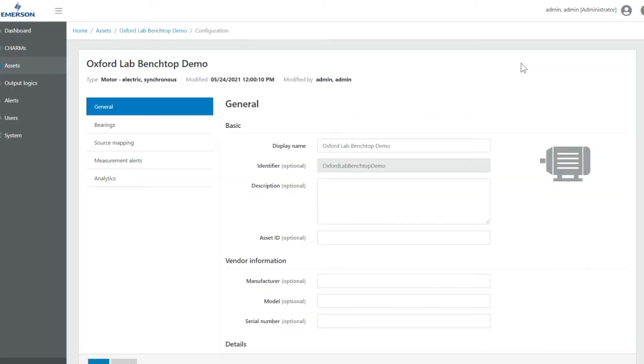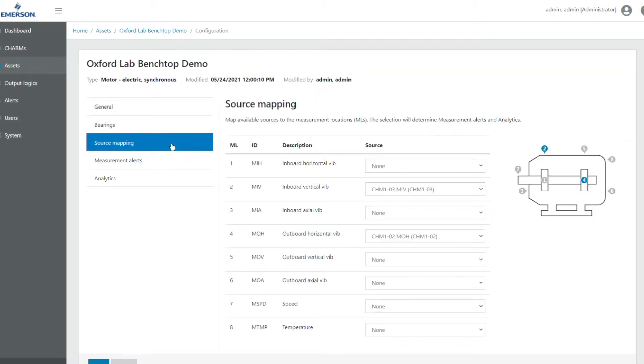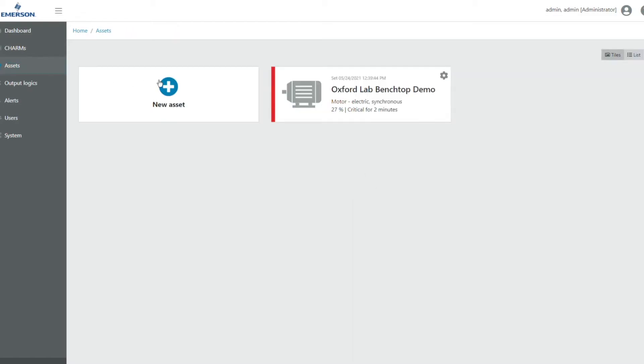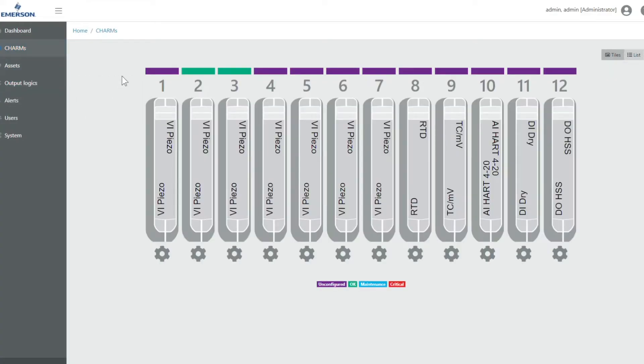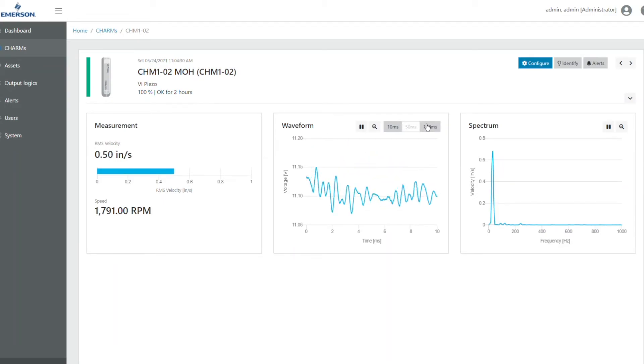Now that you've seen how the system performs, let's take a look at the configuration for the AMS Asset Monitor. The setup process is user friendly and the built-in machine templates allow you to set up your system quickly and easily right out of the box. On our machine we've chosen to monitor the inboard bearing in the vertical axis and the outboard bearing in the horizontal axis. As you can see there are a variety of rotating equipment templates to choose from. For I/O configuration, each I/O module is automatically sensed by the AMS Asset Monitor based on the type of module installed. Here you can see that the first seven slots have VI Piezo modules for accelerometers. On each accelerometer channel, live measurement waveform and spectrum data is displayed.